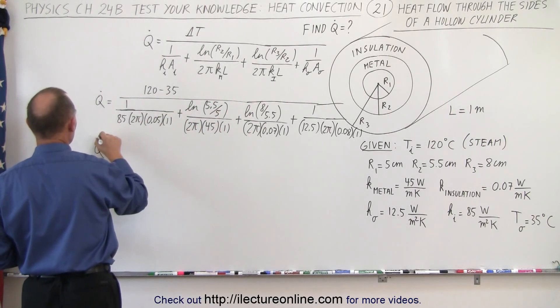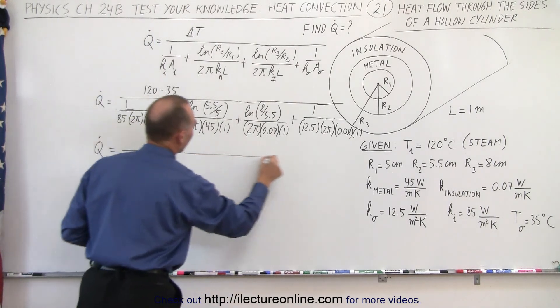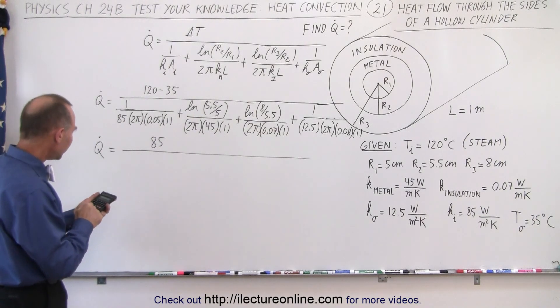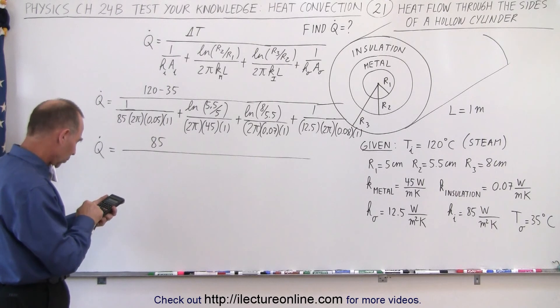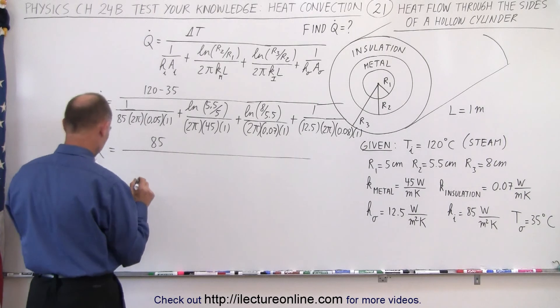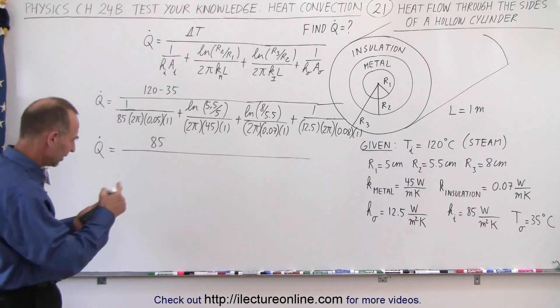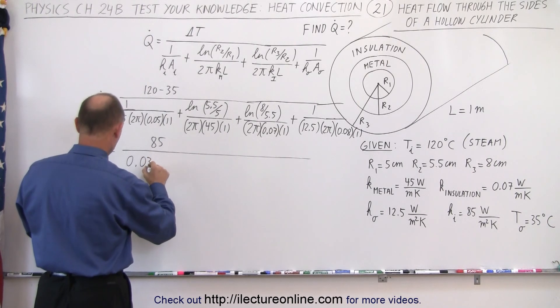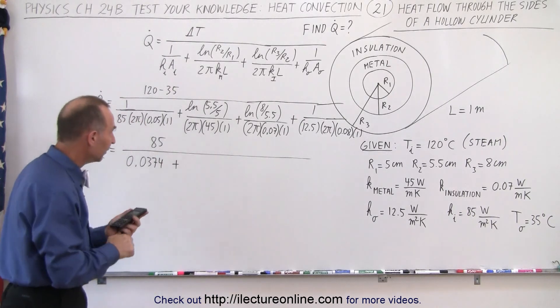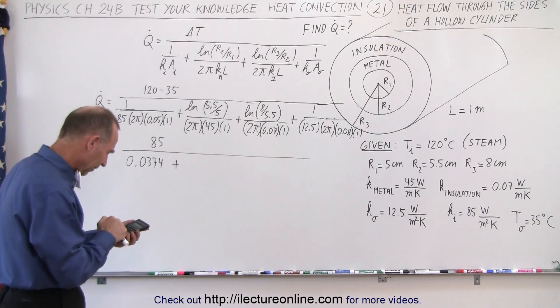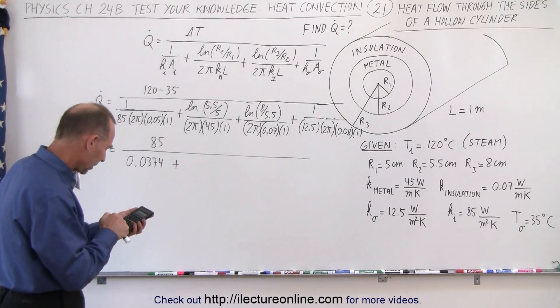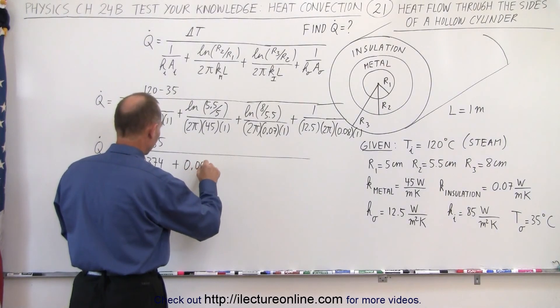So let's find Q-dot. Q-dot is equal to 85 divided by the sum of those terms — let's calculate each one. First: 1 over (85 × 2π × 0.05) gives us 0.0374. Next: the natural log of 5.5 over 5, which is ln(1.1), divided by 2π times 45, gives us 0.000337.